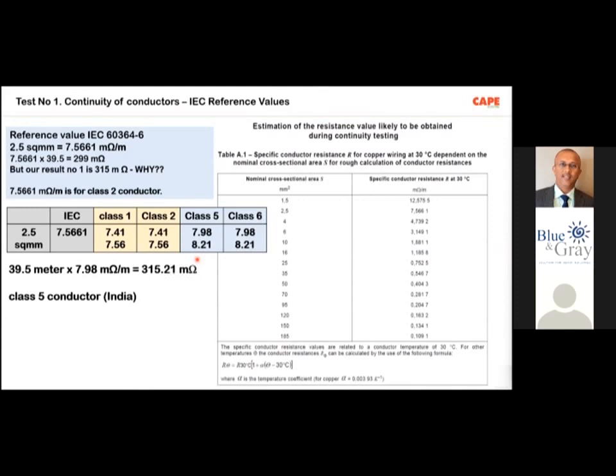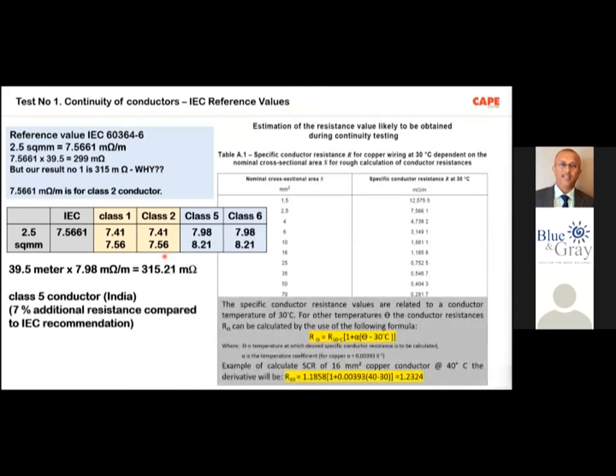Depending upon the installation, depending upon the length of the wire, we are supposed to use derating factors. And now our problem is, for all these derating factors, class 2 wire is considered, which is having a lesser resistance. And if you use a wire with a higher resistance, of course, you will end up with trouble. So we are not supposed to use a wire of class 5. Basically, what I wanted to tell you is, if we do the testing in 100 buildings in India, almost 99.9% the test is failed. So whatever the safety first and the posters which you are claiming is just to show, it's just marketing.